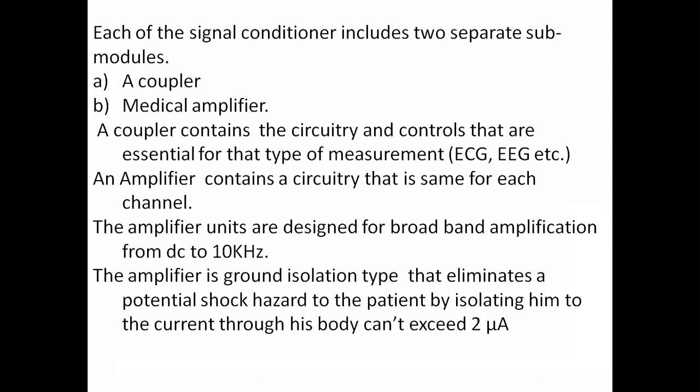In some situations we connect the AC supply to these devices or equipment. If there are any leakage currents, or maybe some short circuit on the equipment, it leads to current flowing to the patient.